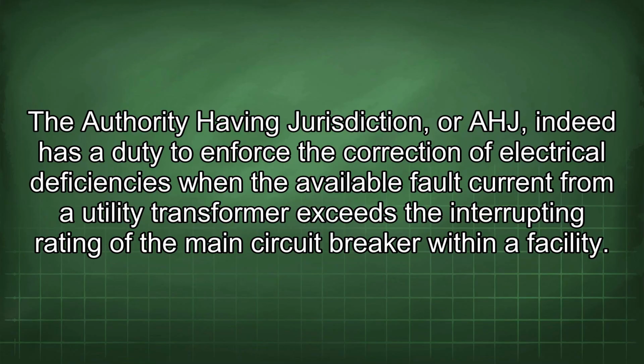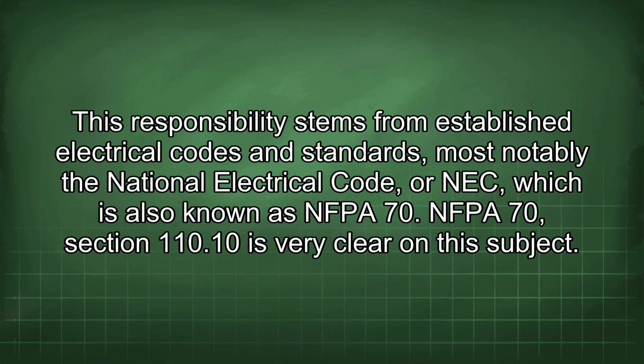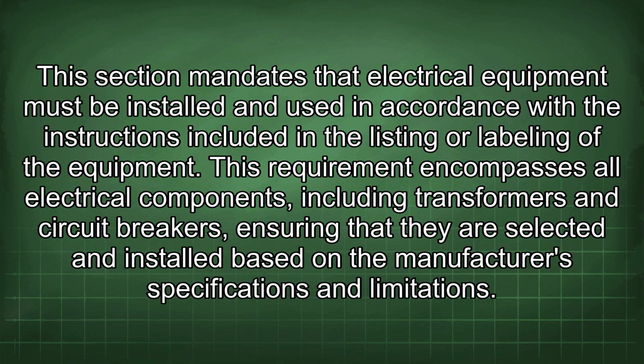The authority having jurisdiction, or AHJ, indeed has a duty to enforce the correction of electrical deficiencies when the available fault current from a utility transformer exceeds the interrupting rating of the main circuit breaker within a facility. This responsibility stems from established electrical codes and standards, most notably the National Electrical Code, or NEC, which is also known as NFPA 70. NFPA 70, Section 110.10 is very clear on this subject. This section mandates that electrical equipment must be installed and used in accordance with the instructions included in the listing or labeling of the equipment.